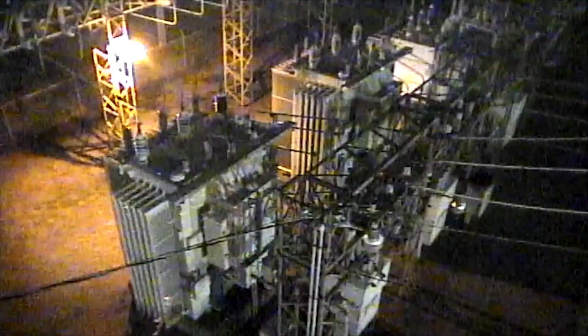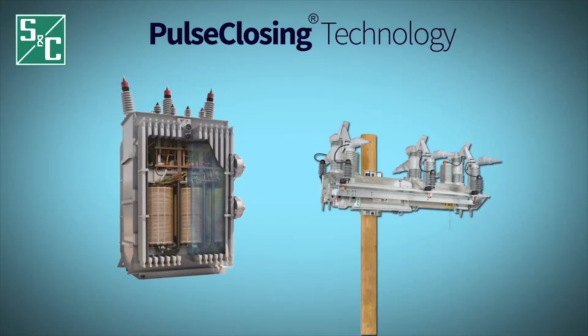Thanks to surveillance footage, we've got footage of a real-life situation which shows a recloser working upstream on a fault. After the third attempt of reclosing, a fire breaks out within the substation, causing a lot of damage. Issues like this happen not only in substations, but they happen in the same way on a distribution feeder. The substation reaps the benefits of pulse closing technology with just a tiny fraction of the mechanical force being put on its windings.